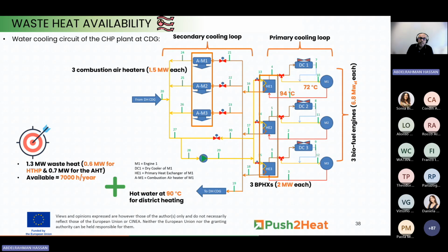If the temperature is higher than 72 here, we can also use dry coolers, as you can see, dry cooler 1 to dry cooler 3, to reduce the temperature further before the water enters these engines again. In the secondary loop, the rejected heat is used to heat the combustion air in these heaters, the air used later in the combustion process. Each one has 1.5 megawatt capacity, and the rest will go to district heating of the CDG at 90 degrees.